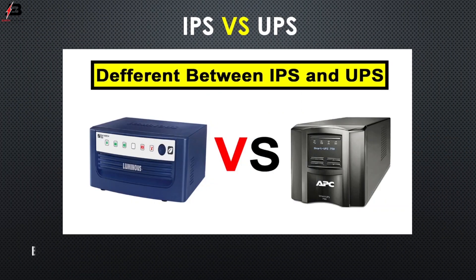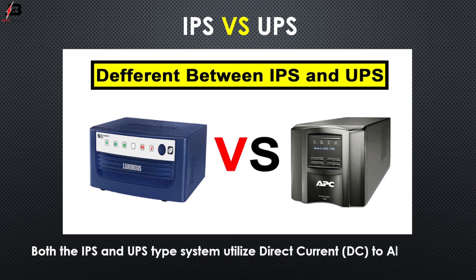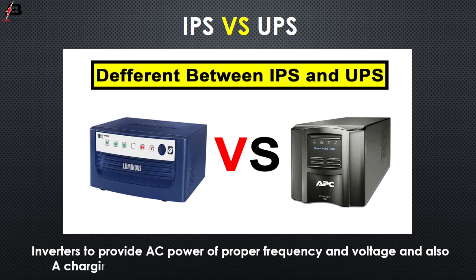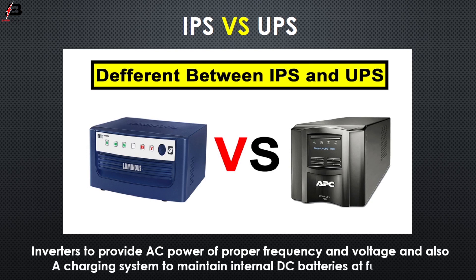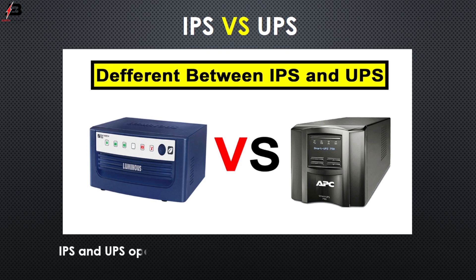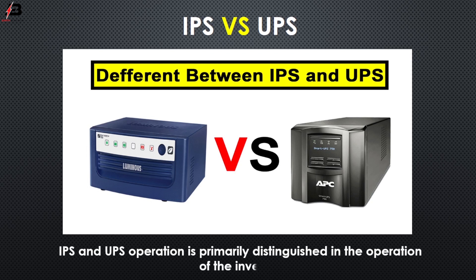Both the IPS and UPS type systems utilize direct current DC to alternating current AC invertors to provide AC power of proper frequency and voltage, and also a charging system to maintain internal DC batteries at full charge. IPS and UPS operation is primarily distinguished in the operation of the inverter.